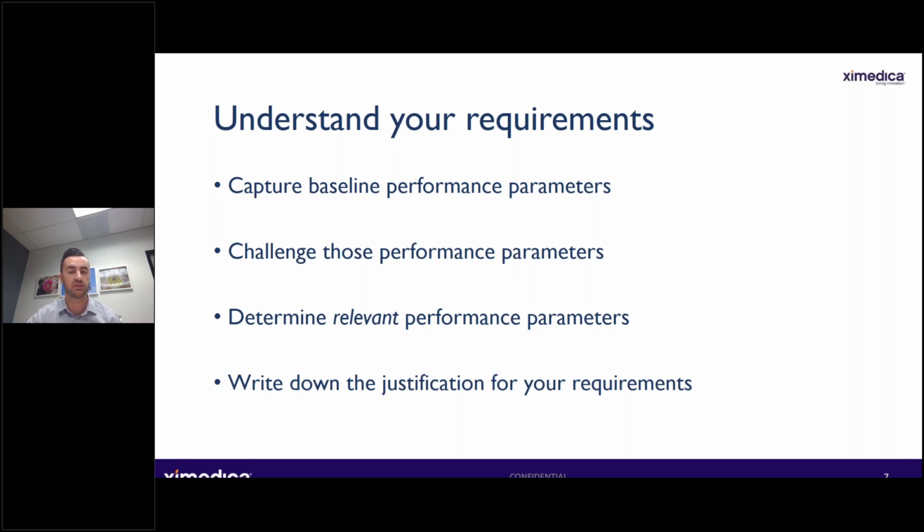From an optics perspective, in the lab, you might be using a $100,000 fluorescent microscope for your detection regime. And this could be far greater than your actual target cost of goods for your instrument. So it can be useful to assess the features and performance parameters of the device you're using and deciding which ones are actually relevant for your assay. This can then, again, allow better hardware choices to be made during the development process.